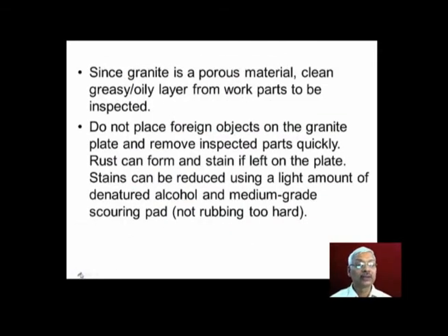Since the granite table is a porous material, we should clean the greasy layer and oily layer from the work parts to be inspected. Otherwise, oil will enter into the pores in the granite. So we should not place foreign objects on the granite plate, and we should remove inspected parts quickly from the table surface. Rust can form and stain if the workpieces are left on the plate.